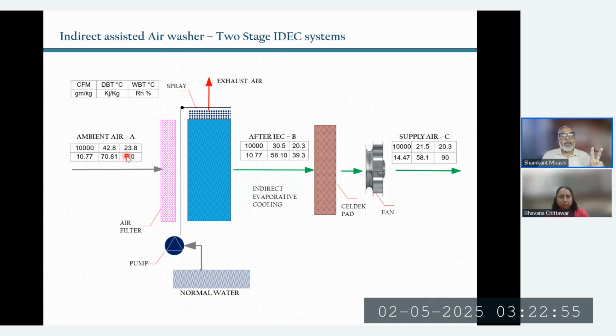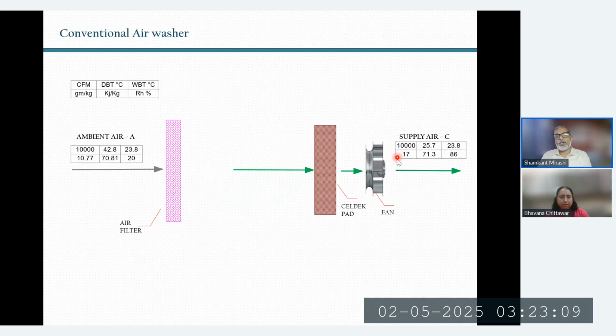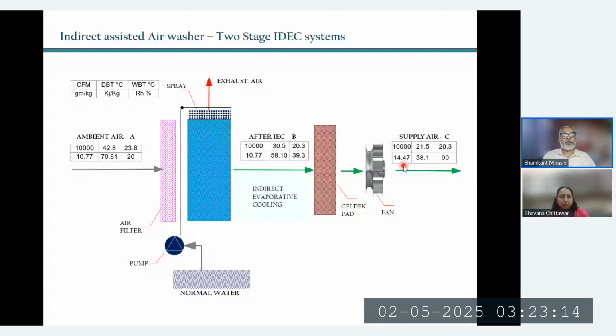We have now cooled the air below ambient wet bulb, which was 23.8. We're able to cool this air now below ambient wet bulb. If you recall the earlier slide, the moisture was very high at 17 grams per kg; now it's only about 14.4-14.5. So we get cold air that is saturated, but at lower moisture content. I had hot and dry air at the input, and I got air which is cold and comparatively dry.